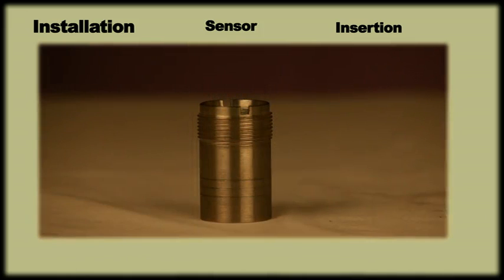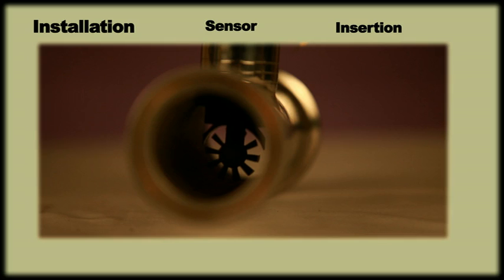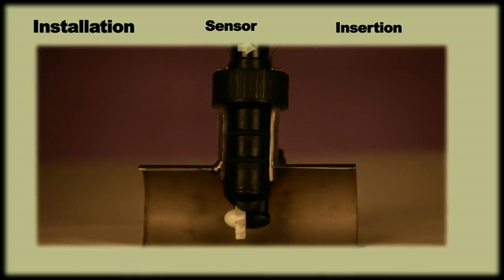These adapters have markings on the body. Depending on the size of the pipeline, it should be inserted to the required depth such that the turbine reaches almost close to the center of the pipeline.